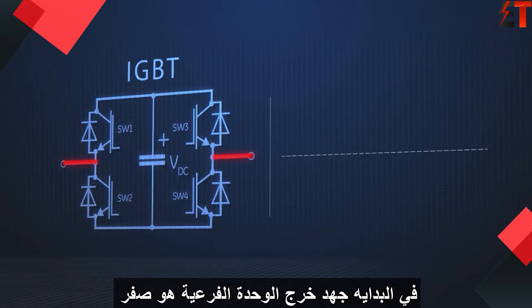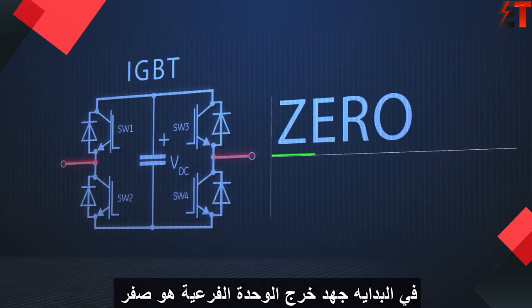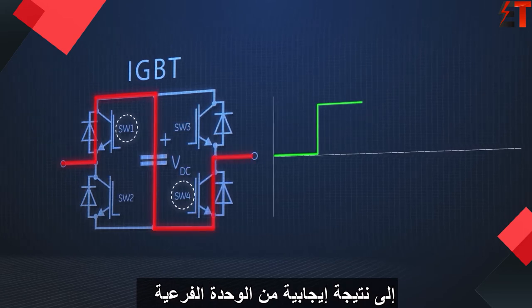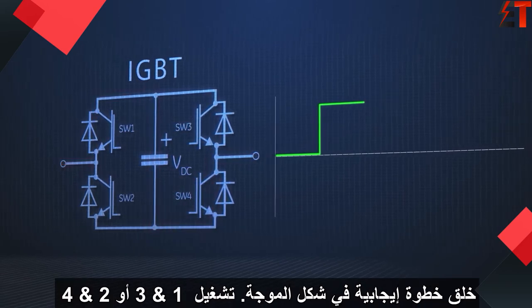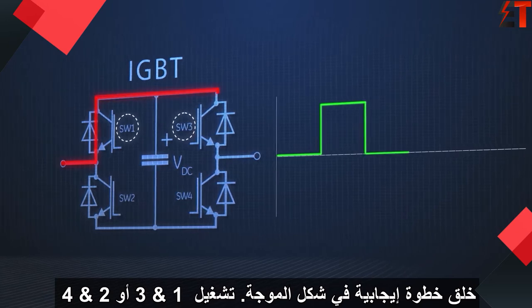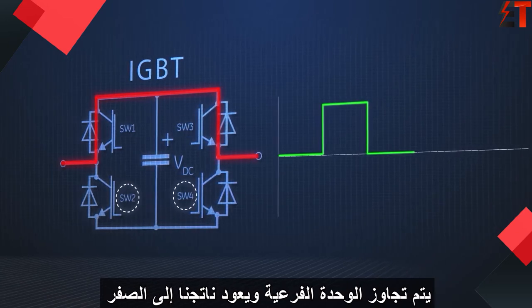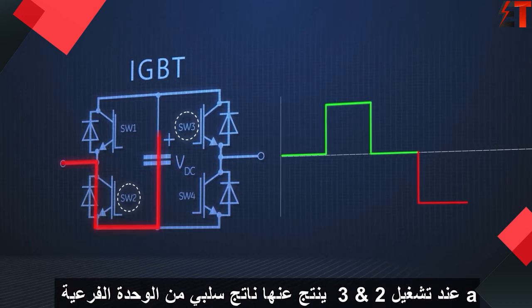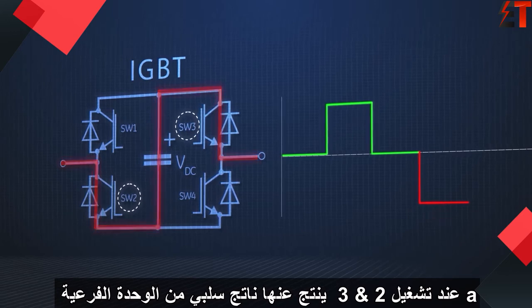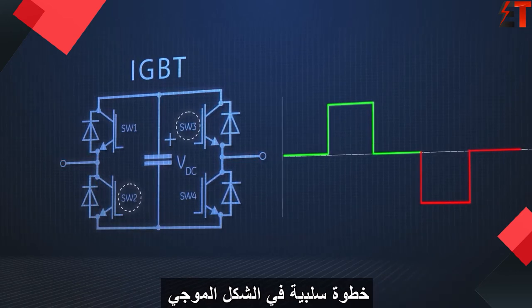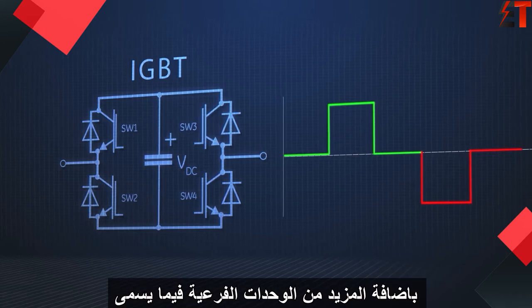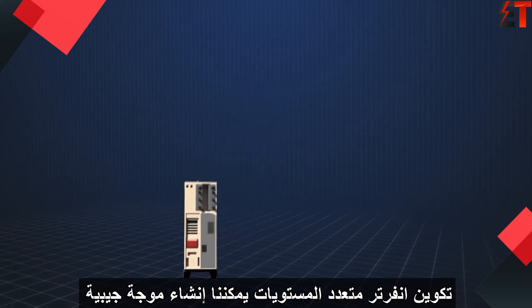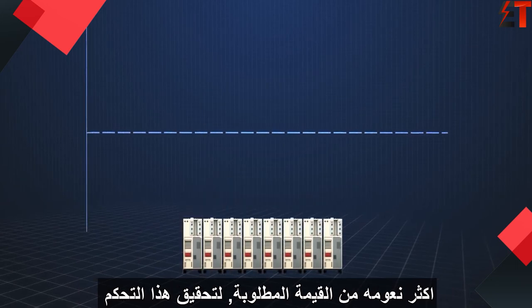Starting in the blocked state, the sub-module output voltage is zero. Turning on IGBTs 1 and 4 results in a positive output from the sub-module, creating a positive step in the waveform. Turning on 1 and 3, or 2 and 4, the sub-module is bypassed and the output returns to zero. Turning on IGBTs 2 and 3 results in a negative output from the sub-module and a negative step in the waveform.